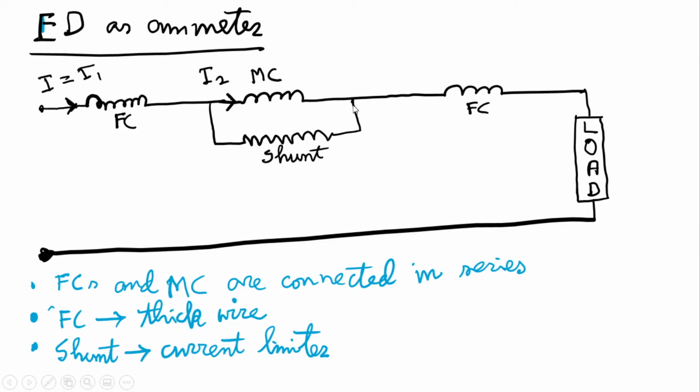And this X term is frequency dependent. So at a particular frequency your device may work well, but at another frequency the value of X becomes different. So Z becomes different. So V by Z becomes different. Same current flowing, but due to the frequency the current is actually becoming different. So that's why, to eliminate that error, the L by R ratio of both these two branches should be made as nearly equal as possible.